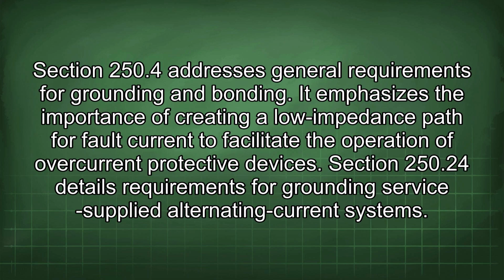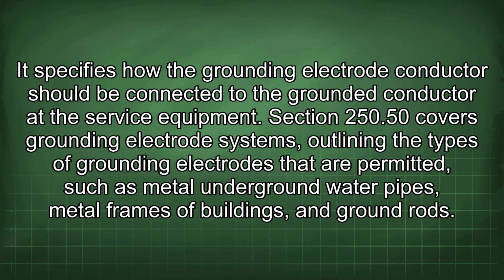Section 250.4 addresses general requirements for grounding and bonding. It emphasizes the importance of creating a low impedance path for fault current to facilitate the operation of overcurrent protective devices. Section 250.24 details requirements for grounding service supplied alternating current systems. It specifies how the grounding electrode conductor should be connected to the grounded conductor of the service equipment. Section 250.50 covers grounding electrode systems, outlining the types of grounding electrodes that are permitted, such as metal underground water pipes, metal frames of buildings, and ground rods.